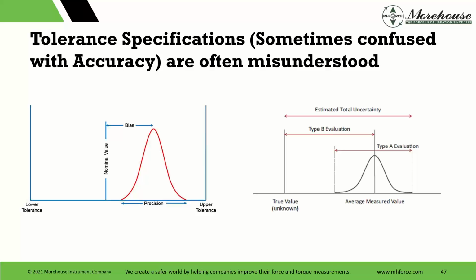So when we start looking at this, if somebody says to me, I need you to calibrate this device, and I want you to do an E74 cal, and I also want it to be within 0.05% of reading, I say, what now? The standard's written so you use correction factors and coefficients. So you use these coefficients. They predict your curve. You should be dead nuts on everything. But then you find out that, oh no, they're reading it different. So that's a whole other tangent of errors.